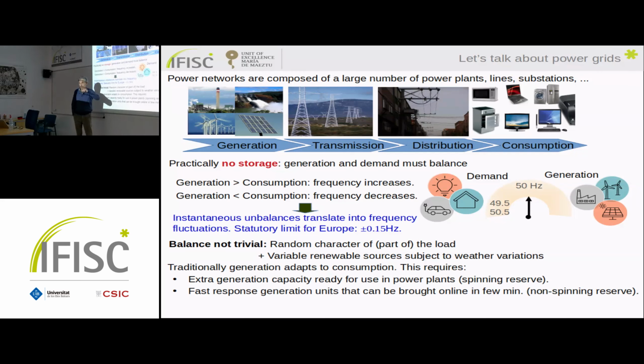And you have fast units that can start from cold very fast when needed, which is what is called the non-spinning reserve. It's a reserve that isn't spinning at that time but can be switched on whenever needed. Like, for instance, when there is a power shortage, the diesel generator starts, which takes a couple of minutes, and then you have main power there. In the meantime, if you want no interruption, this has to be maintained by a battery or storage system that covers the time the generator needs to start. So with conventional power plants, you might increase the power a little bit above normal, and meanwhile start another power plant which is fast to start, and then recover this extra power. That's the non-spinning reserve.